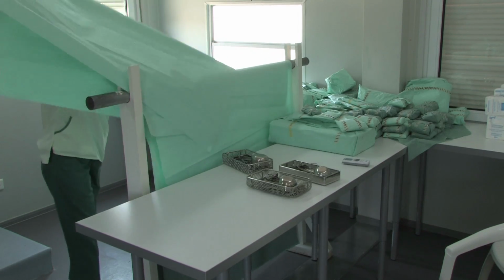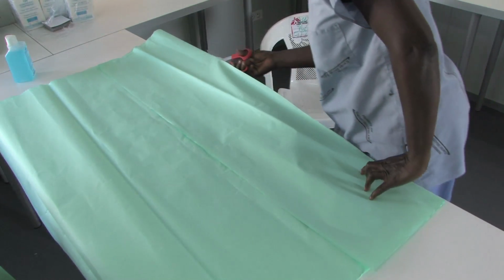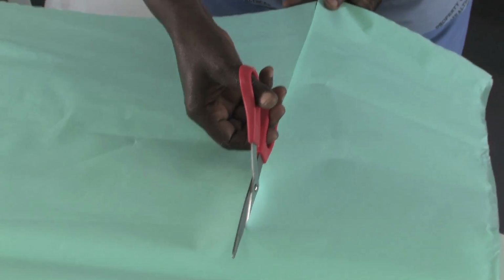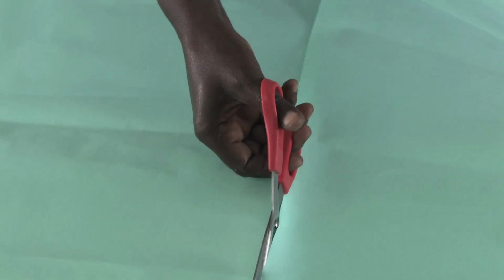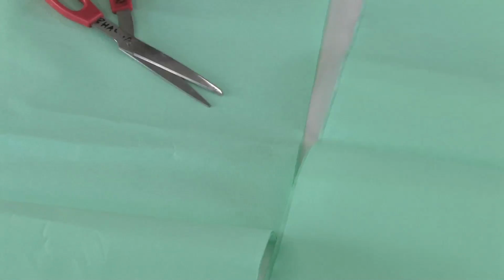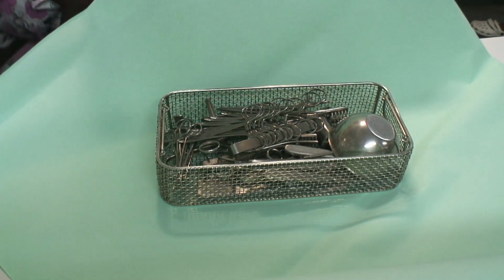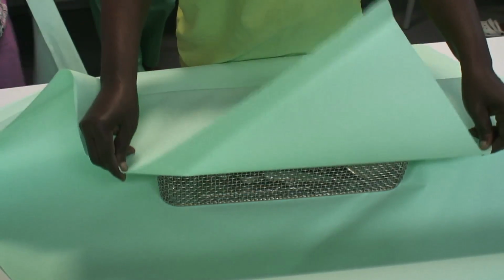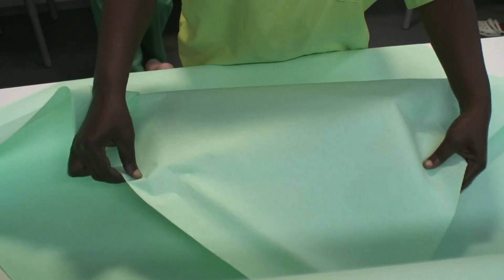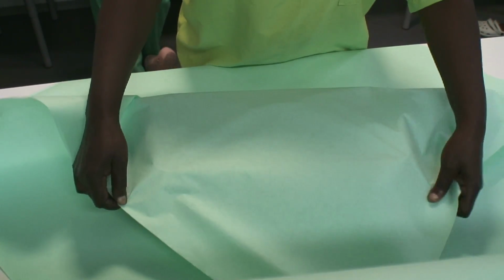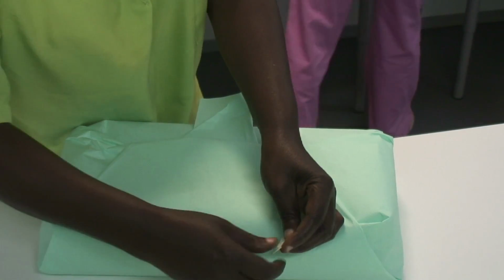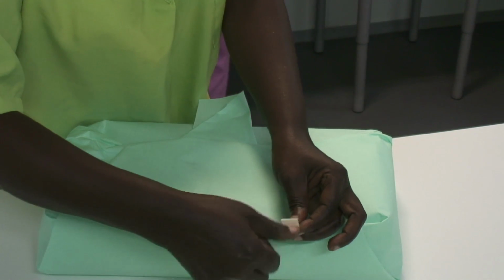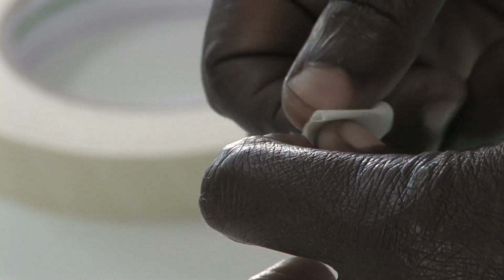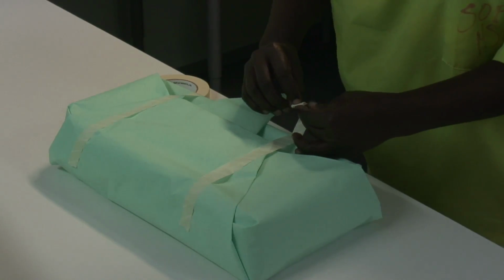Adapt the size of the sheets to the size of the basket or box to be wrapped. If necessary, cut the sheets to the right size. A sheet that is too small will not adequately protect the instruments, and one that is too large will form folds and channels that will retain water when the steam condenses, preventing drying. Use the correct folding technique so that the package can be opened without loss of sterility.